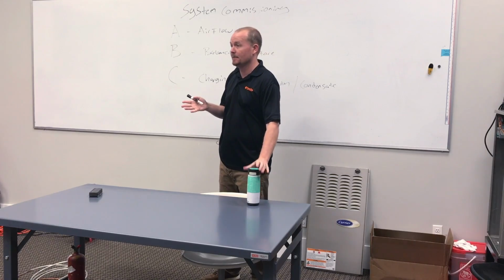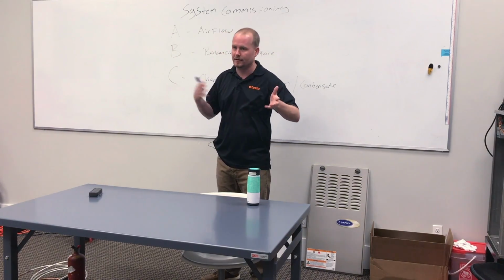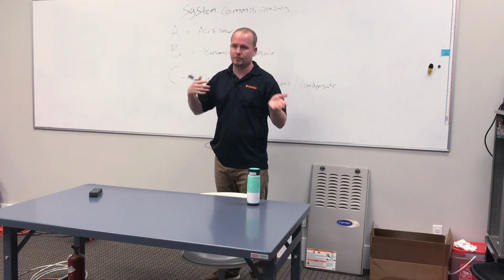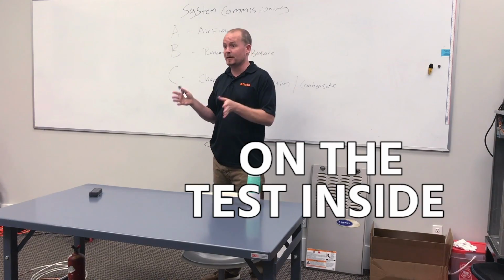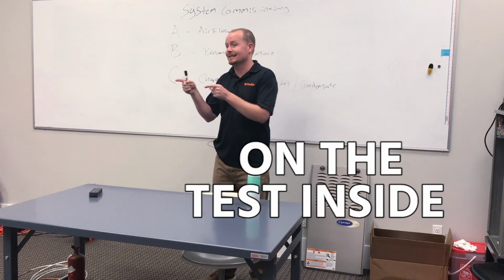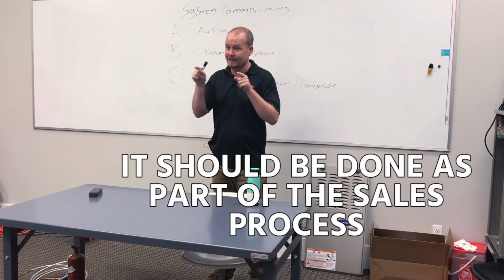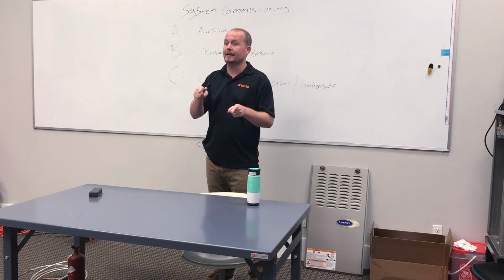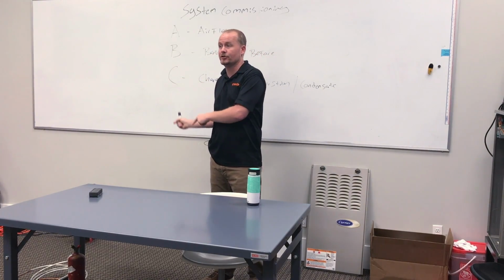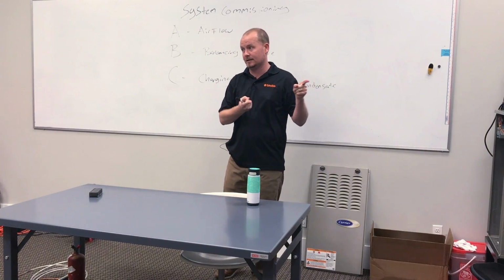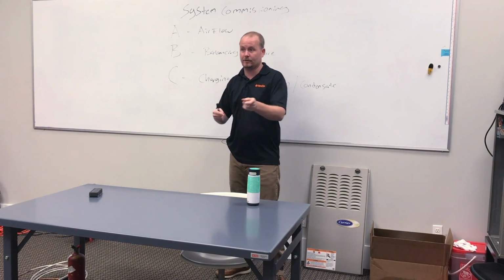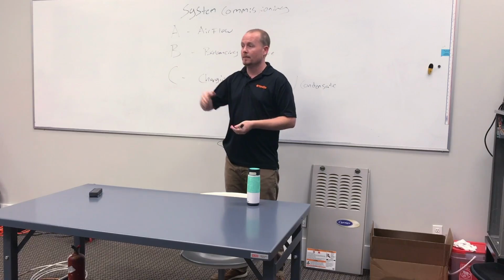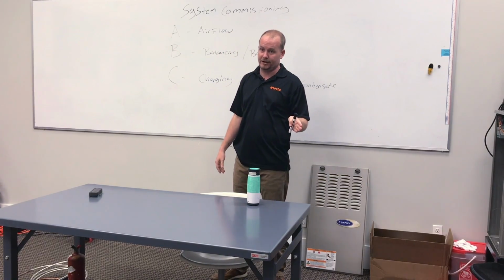Now, sometimes that can't be done the same day because you're getting busy and things are going wrong, and oops, I don't have the hood, and oops, whatever, that stuff happens, especially on the test inside. But on the test inside, that should be done as part of the sales process, if at all possible. And if it isn't done as part of the sales process, then the salesperson needs to make sure that it's done as part of the installation process. Even if they've got to set up for a service tech to run by, or they've got to run by, or whatever. But test in, test out with duct changes.